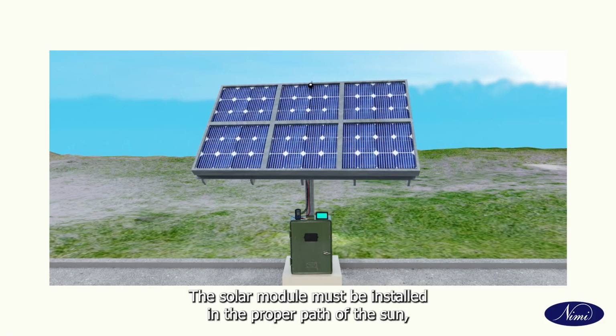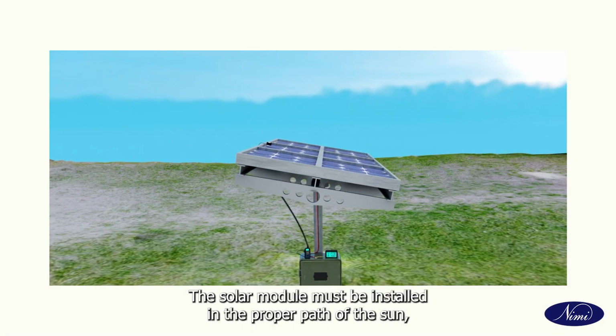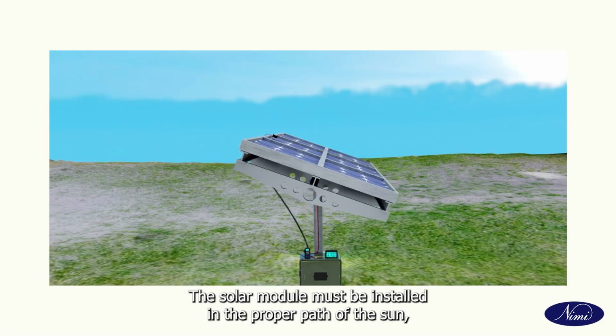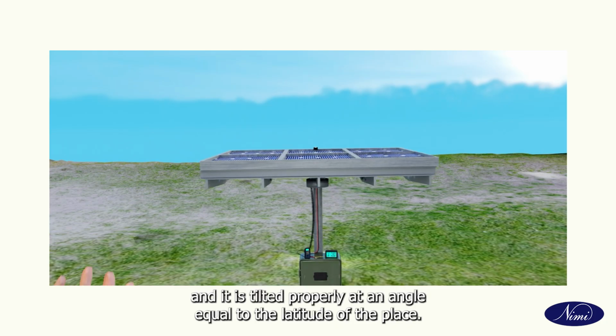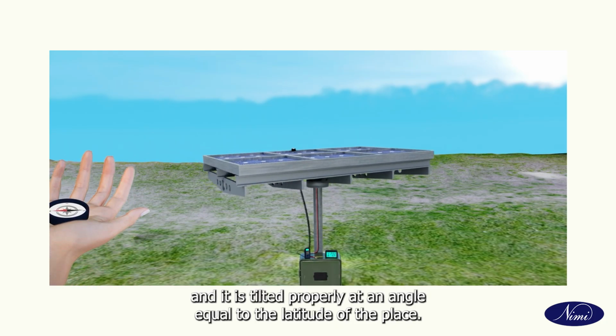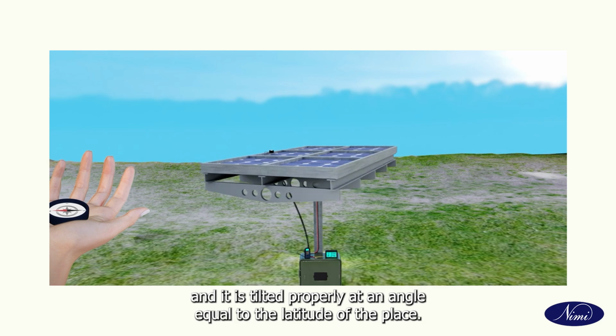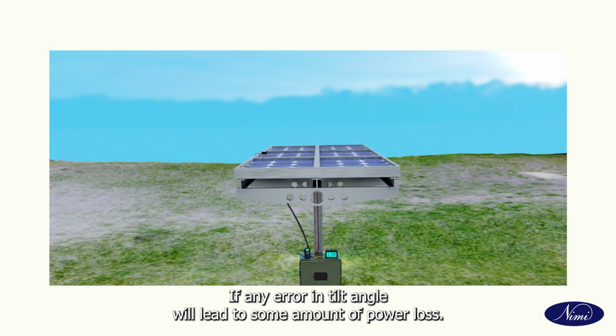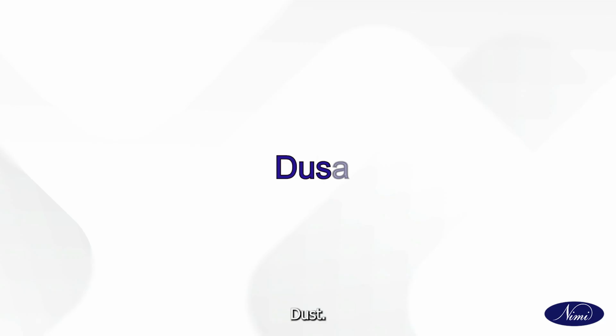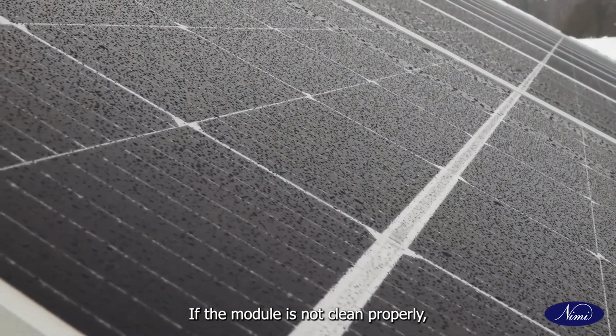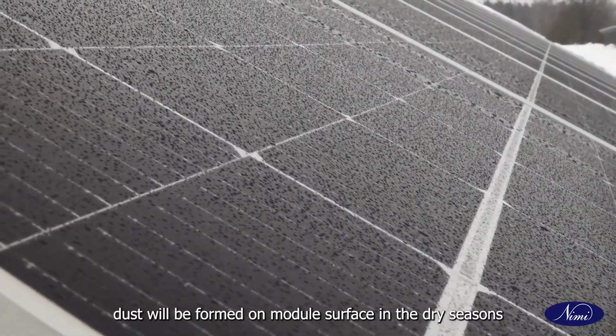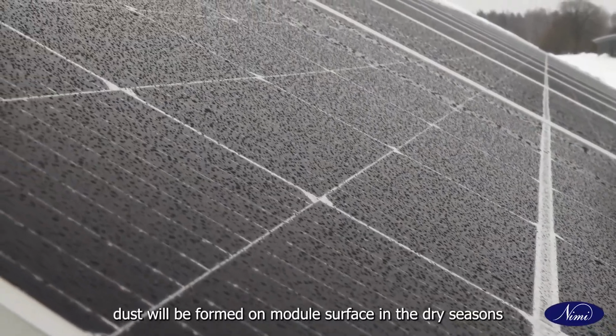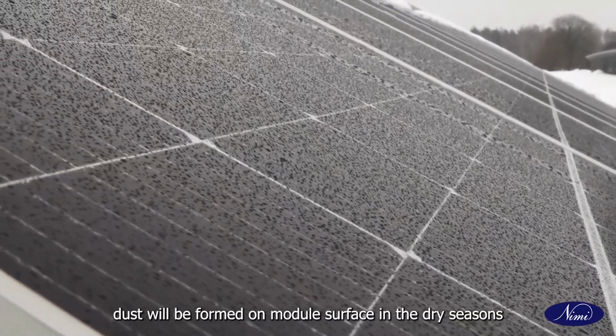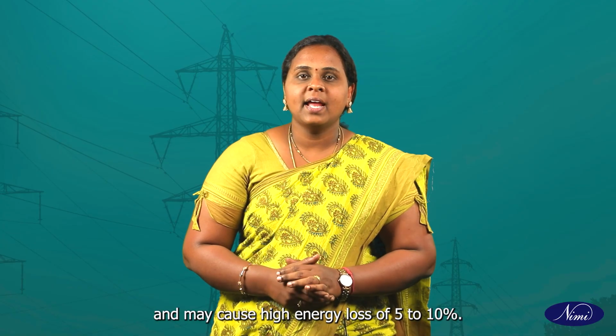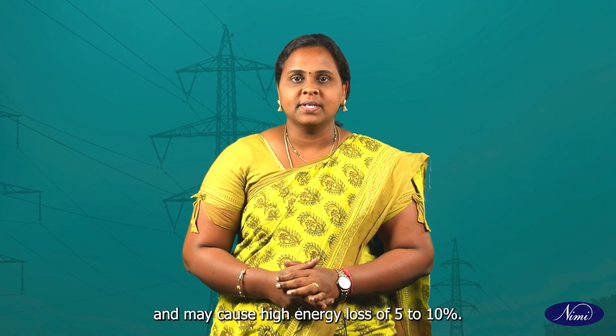Tilt angle. The solar module must be installed in the proper path of the sun and it is tilted properly at an angle equal to the latitude of the place. Any error in tilt angle will lead to some amount of power loss. Dust. If the module is not cleaned properly, dust will form on the module surface in the dry seasons and may cause a high energy loss of 5 to 10%.